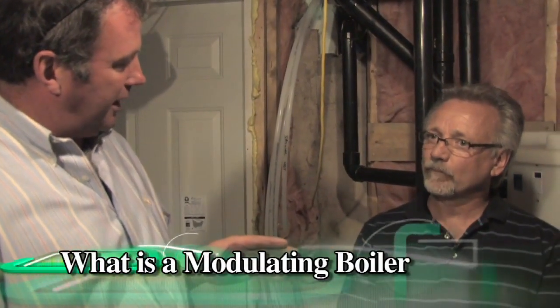You mentioned modulating and condensing — the viewers may not be familiar with those terms. A modulating boiler modulates to whatever temperature is desired. So if you have a regular appliance that's say 90,000 BTUs and it fires at 90,000 BTUs every time, a modulating boiler will kick in a lot lower and modulate to whatever is needed based on how long it's running — so you're not burning full capacity all the time. If the house requires 40,000 BTUs, the boiler will run at 40,000 BTUs.